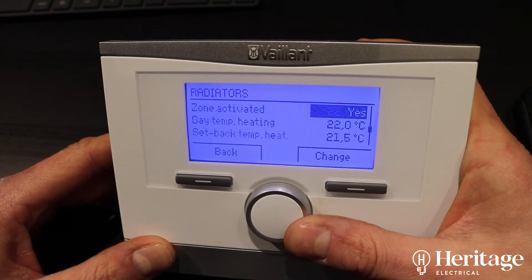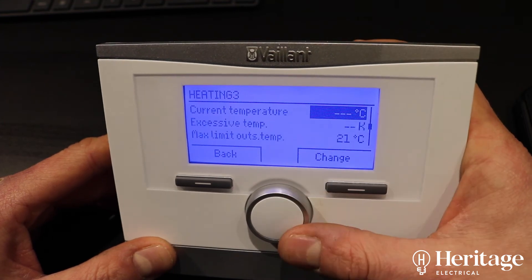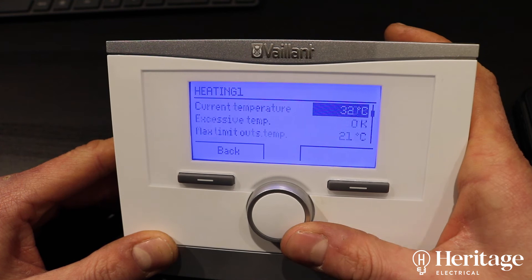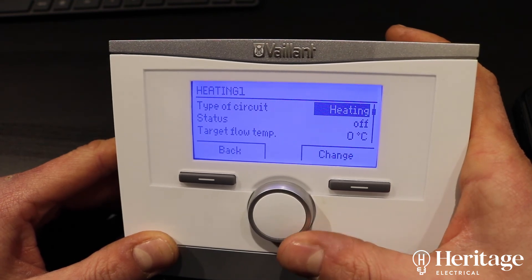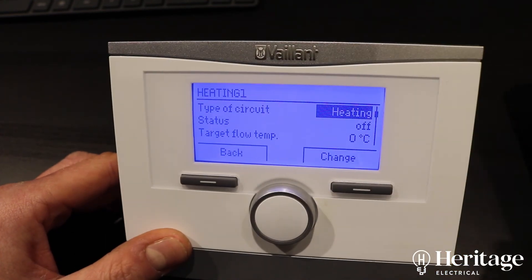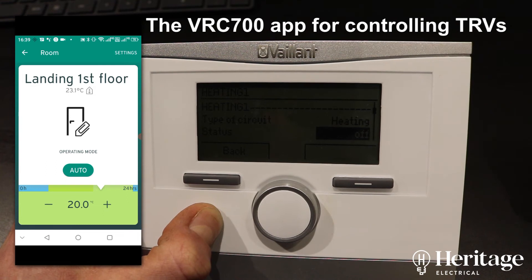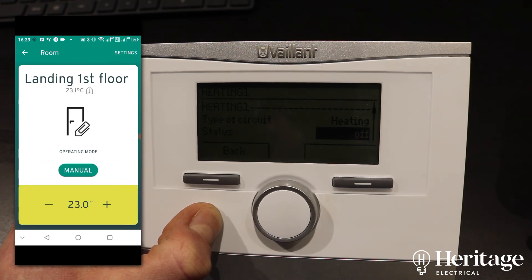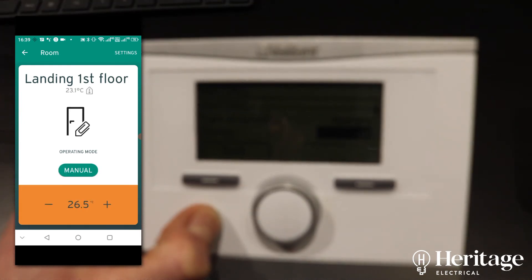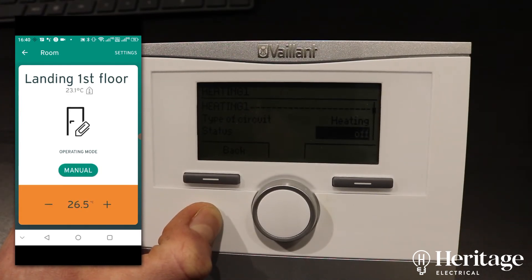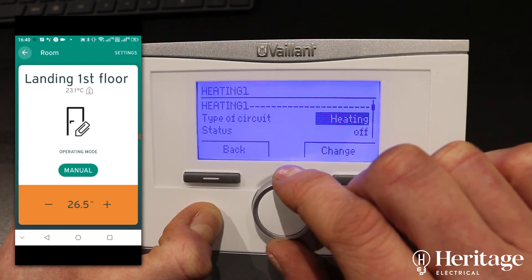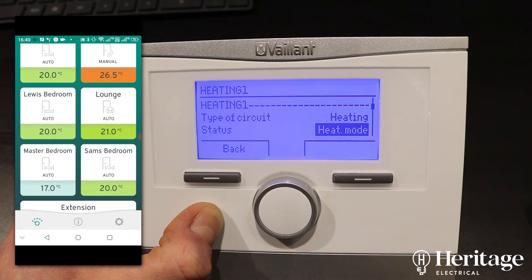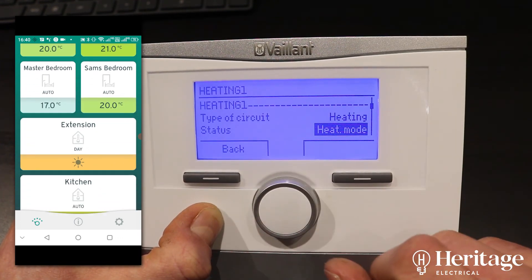If we scroll back up to the radiators — heating one — you can see the status is currently off because all those thermostats are satisfied. If we pick, say, landing first floor, you can see the temperature in the room is currently 23.1°C. I'm just going to nudge this up past that, and hopefully we should see the boiler start to call for heat. You can see now that we've put that TRV into manual mode, overriding the programme, and that circuit is now calling for heat.